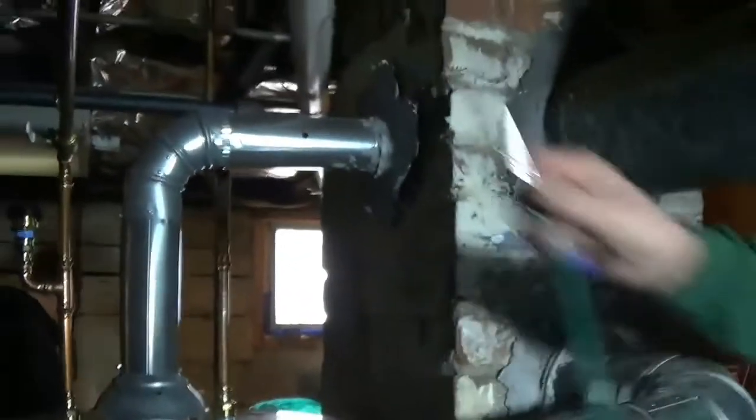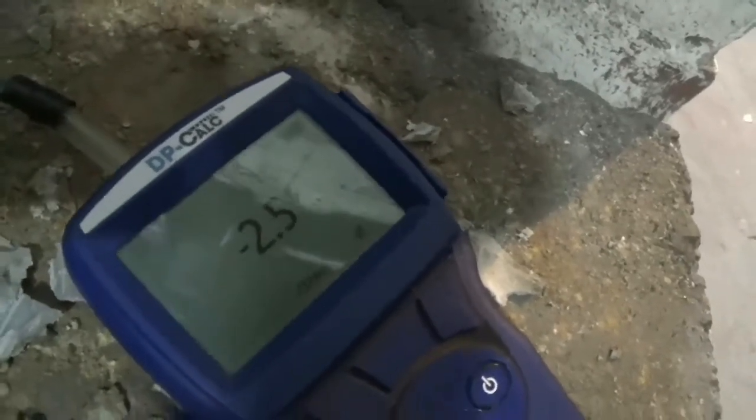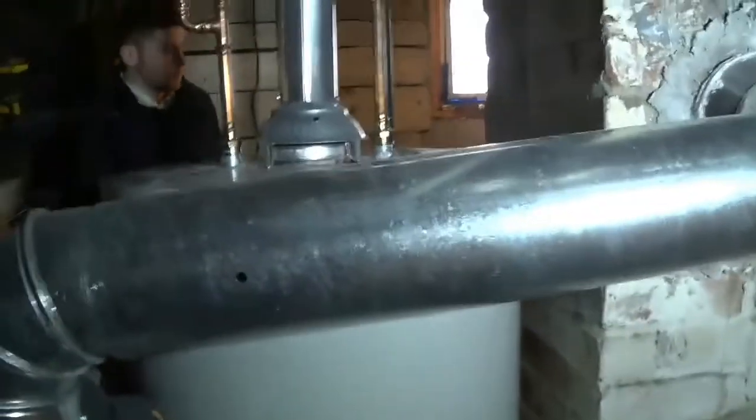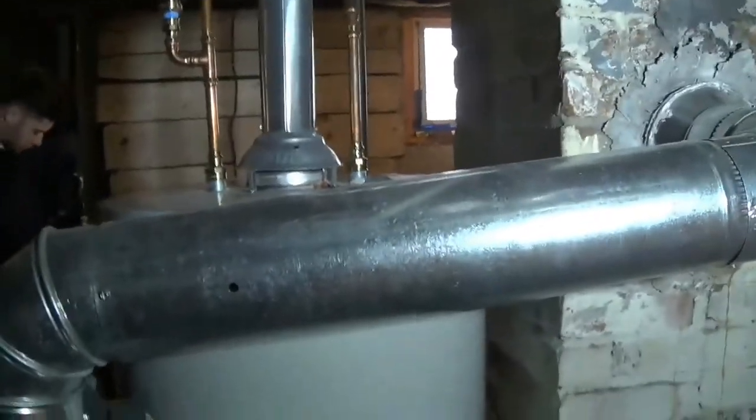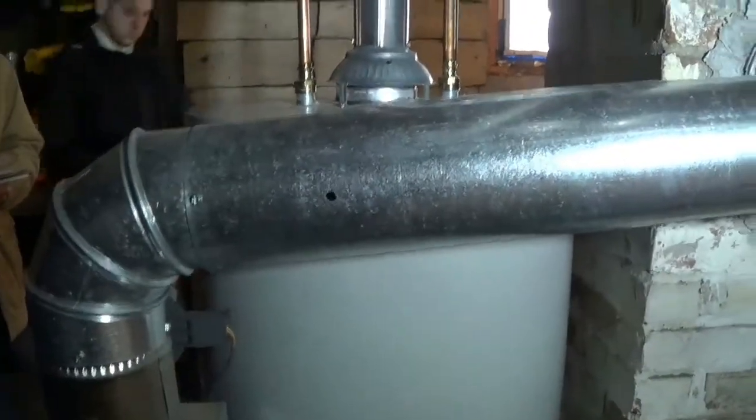All right. Now let's measure the equipment. So we've got the boiler itself. Oh, by the way, sorry. We got spillage fail with the boiler helping. The draft for your domestic hot water is actually not as good as when the boiler is running, so the boiler running hurts the water heater a little bit. Now it's actually getting pretty close to the same. So minus 2.5 for the draft on the domestic hot water heater with the boiler helping, right? So that's that second spot, minus 2.5.